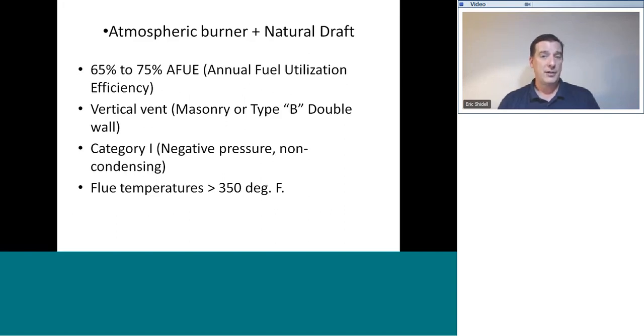All of our flue vents are going to be vertical, straight up and down. There may be an offset somewhere in the middle of the pipe, but generally it's going to be a vertical arrangement. And how much of an offset we can have, all that comes out of the National Fuel Gas Code or the International Fuel Gas Code or the International Mechanical Code. The venting tables need to be followed. You will find problems with venting and drafting if those tables are not followed, and that includes angles of offset, lengths, distances of offset, diameters of pipe, lengths of pipe, all that stuff is in there.